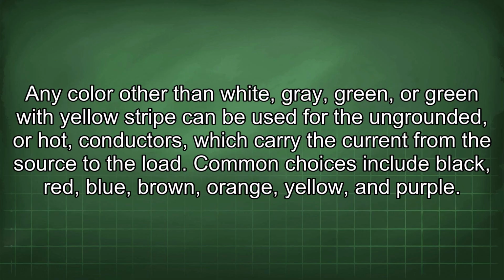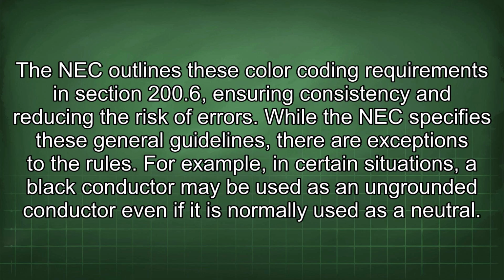Any color other than white, grey, green, or green with yellow stripe can be used for the ungrounded, or hot, conductors, which carry the current from the source to the load. Common choices include black, red, blue, brown, orange, yellow, and purple. The NEC outlines these color coding requirements in section 200.6, ensuring consistency and reducing the risk of errors. While the NEC specifies these general guidelines, there are exceptions to the rules.